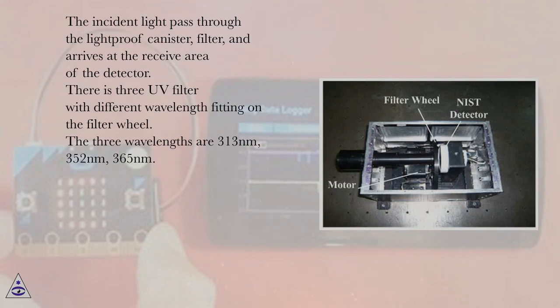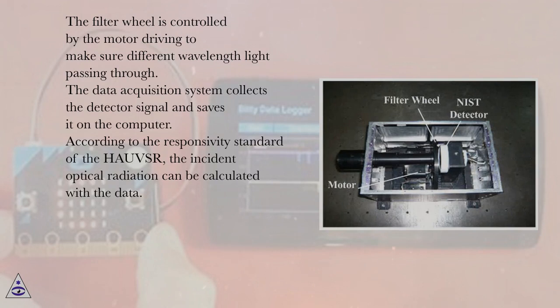The incident light passes through the lightproof canister and filter, and arrives at the receive area of the detector. There are three UV filters with different wavelengths fitted on the filter wheel: 313 nm, 352 nm, and 365 nm. The filter wheel is controlled by a motor drive to select different wavelength light. The data acquisition system collects the detector signal and saves it to a computer, and according to the HAUVSR responsivity standard, the incident optical radiation is calculated from the data.